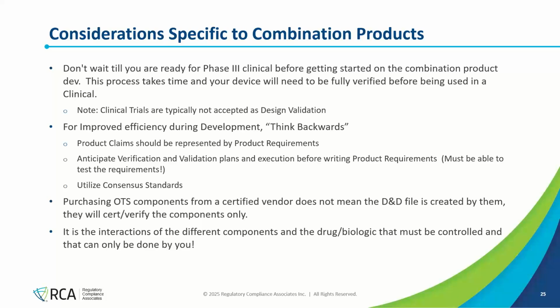So sometimes it helps to think backwards. Think about the claims you want to put in your labeling. Think about the specific measurements, notes, numbers that go in the labeling, and those end up being your product requirements. Once you have your requirements clearly defined, you know exactly what testing you need to do, because every requirement requires testing. And then utilize a consensus standard. There's ISO standards for syringes and needles and luer locks and everything else. And if you can simply say must be compliant with 11040, must be compliant with 80369, then you can cut the corner on some of that stuff.